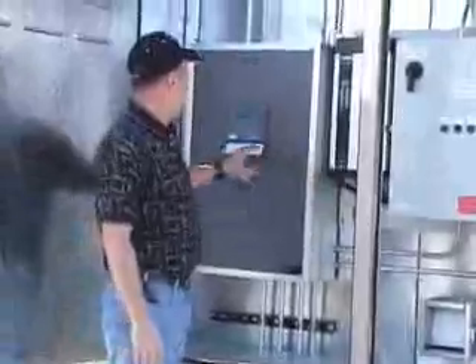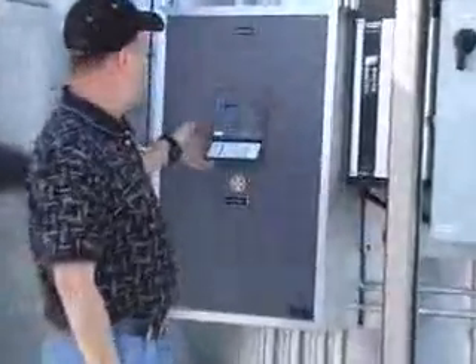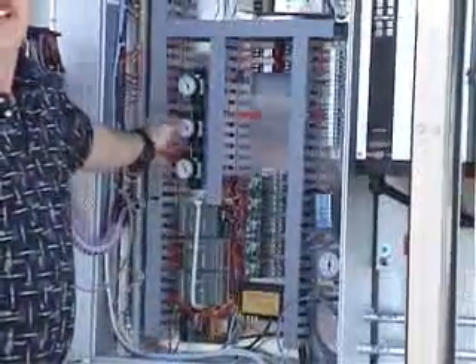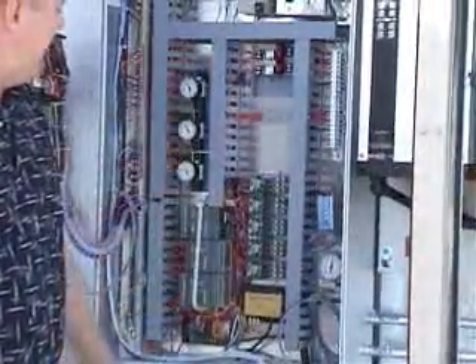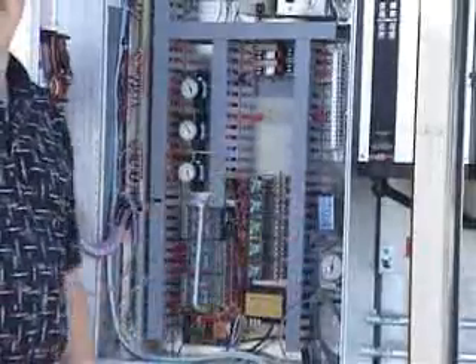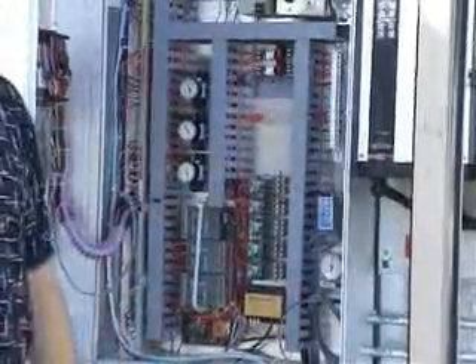This panel here contains all of the temperature control devices. We have a digital control system here on the front with controls. Inside we have basically all the guts of the unit. We have pneumatic actuators to control the dampers and the heating and cooling valves. We have relays that power up and turn various things on and off within here.